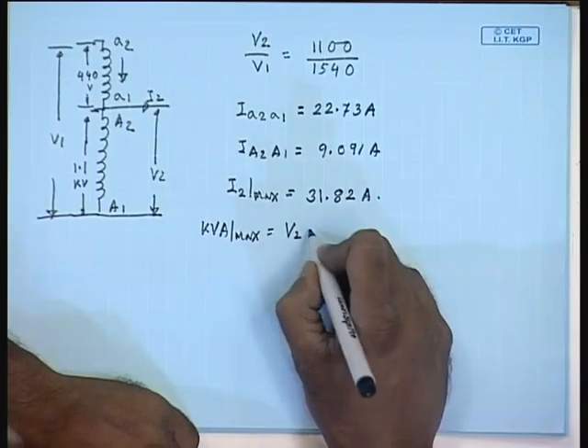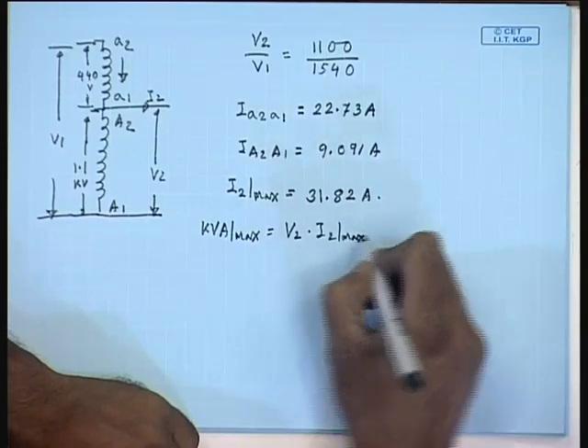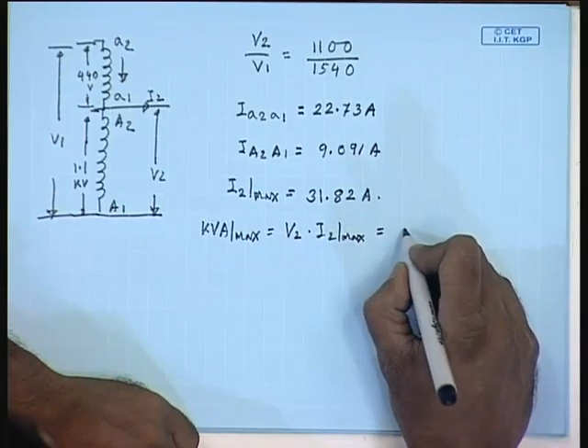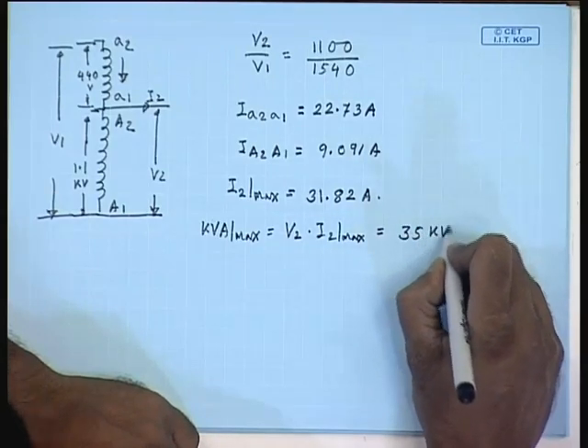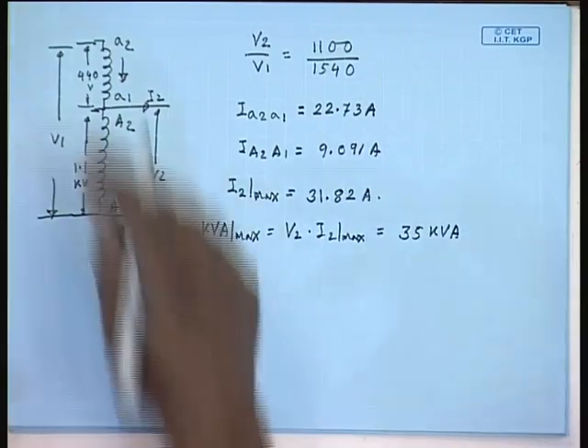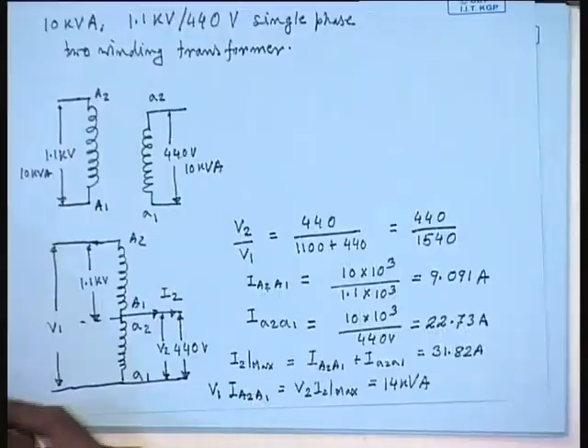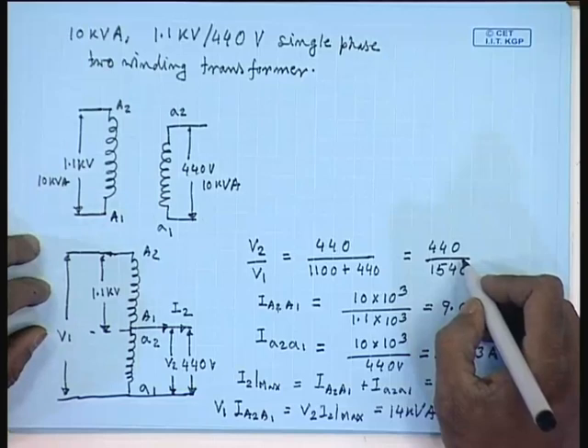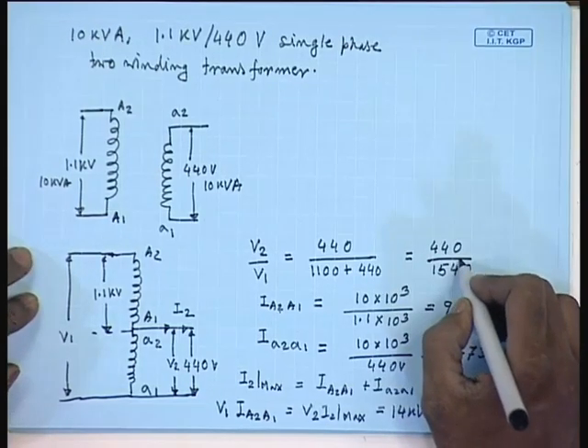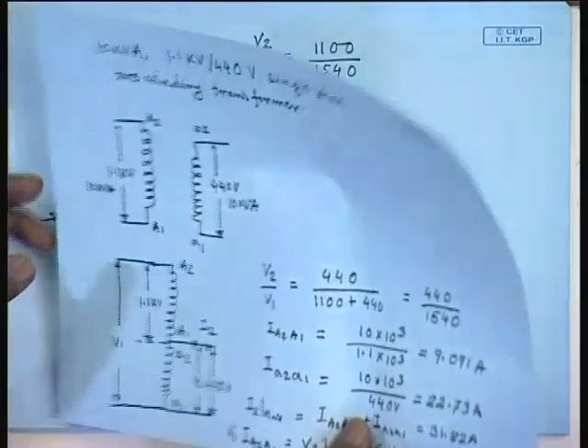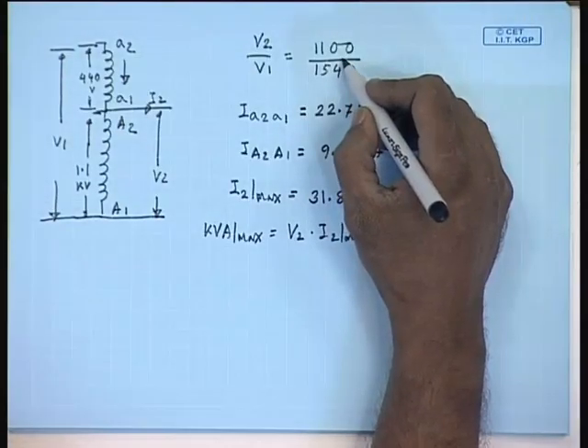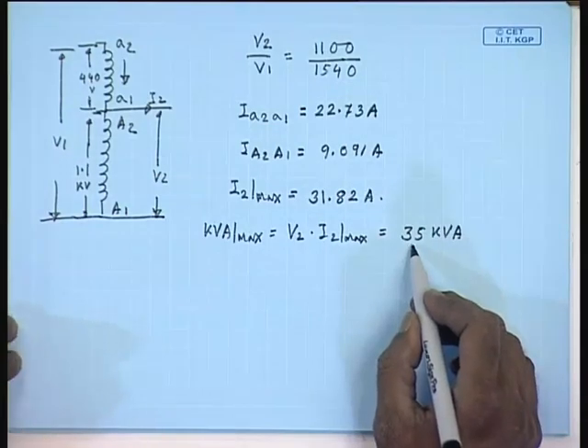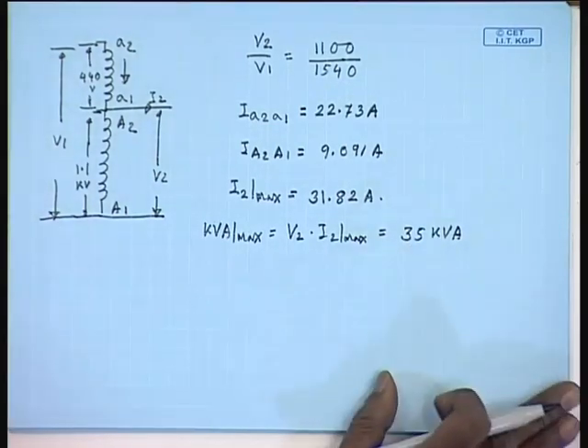Now, the maximum kVA, that is V2 into I2 max, comes to about 35 kVA. So, a 10 kVA two winding transformer can supply 35 kVA when connected as the auto transformer. It is easy to see here that the value of alpha was much lower than 1, hence the increase in the kVA was not all that great. Here the value of alpha is close to 1, hence we get almost 3.5 times increase in the kVA rating of the auto transformer.